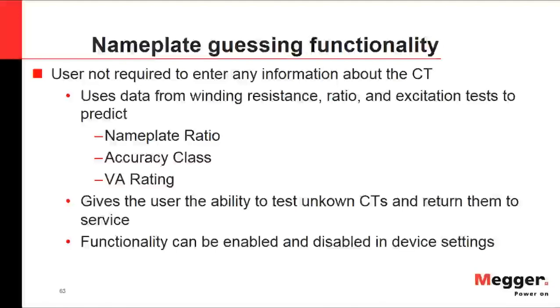One problem you may encounter is a CT in the field whose nameplate is not readable, and engineering drawings may also be unavailable. In this case, the MRCT's nameplate guessing functionality can predict the nameplate ratio, accuracy class, and VA rating from the test measurements.